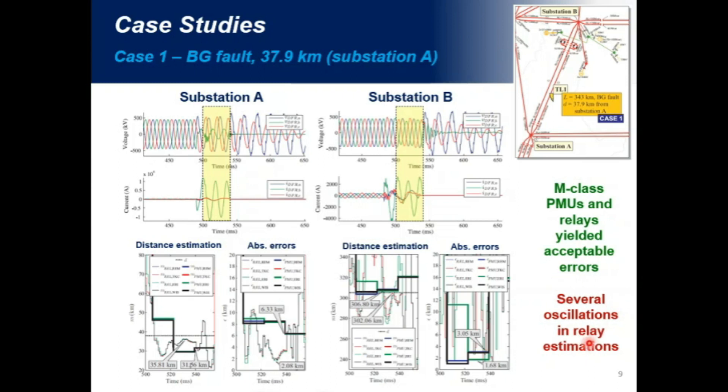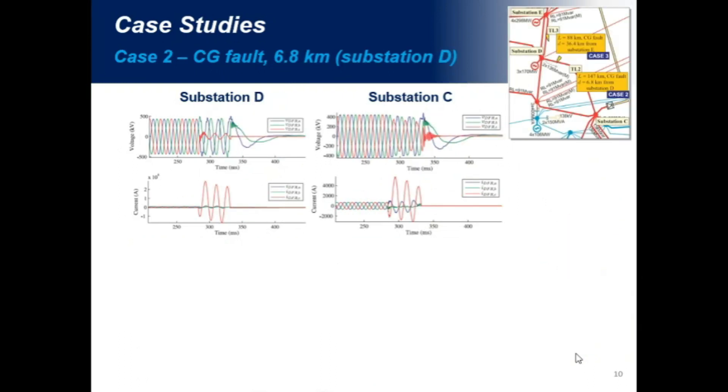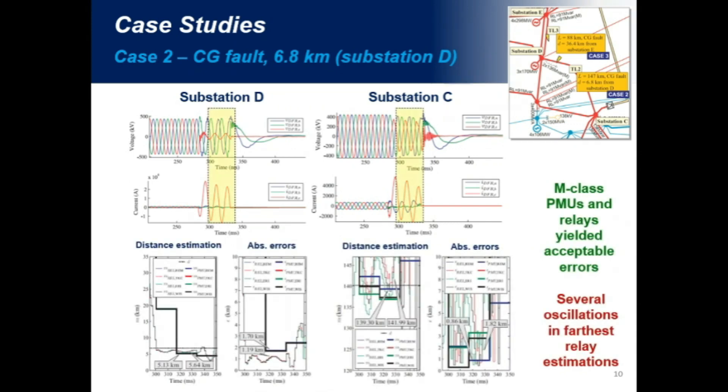In case two, we have a very similar behavior. Again, the errors here at substation D did not exceed the order of two kilometers for both PMU and relay estimations. And at the other side, at substation C, we obtained even more accurate estimations, such that errors did not exceed the order of 1.8 kilometers. Again, M-class PMUs yielded acceptable errors, and we could verify the oscillations, more oscillations in the relay during the analysis of this case.